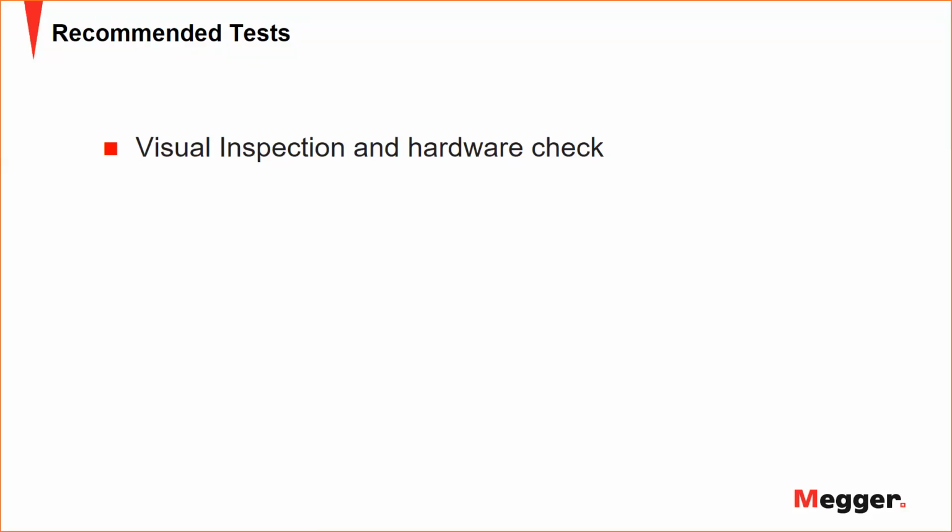Now, in numerical relays, there is always a healthy indicator or watchdog contact. And in commissioning stages in particular, I see this done, doing a hardware check, where in the relay you have binary inputs, binary outputs, and the power supply circuitry. You can test these even without a secondary injection test kit. You just go to the relay. They allow you a test mode in the relay where you can close all the contacts and check them with a continuity checker. Check all the contacts are coming in when you close them.